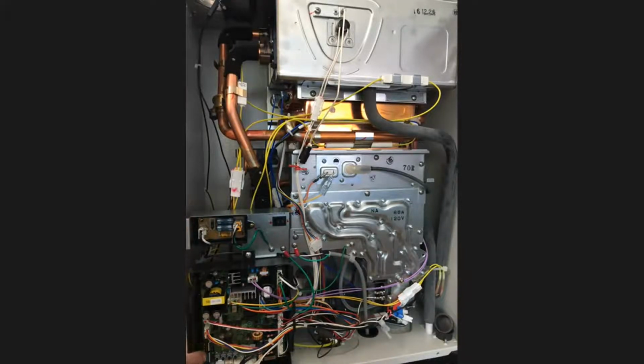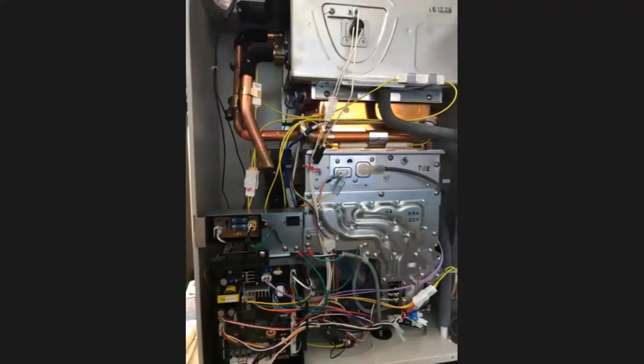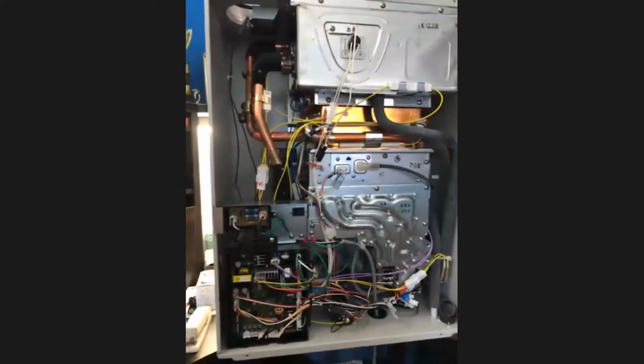That's going to be part of your initial installation. Plan your venting out when you first get started so you don't box yourself into a corner. They limit the number of 90-degree elbows you can use, for most of these it's no more than 5, regardless of your vent run. You'll also have to select the length of your vent run on your dip switches. So those are considerations you'll have to make, probably before you get too far into it.